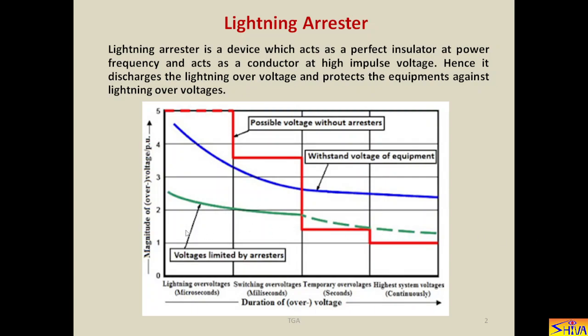Now let us see from this diagram how it protects the electrical equipments. So this is the over voltage coming in the system if it is not arrested. This is of very high magnitude. This is the withstand voltage of the equipment, that is nothing but the basic impulse level of the equipment being protected. So it indicates that in no case should the over voltage coming in the system cross this value. Therefore we have to arrest the lightning over voltage well before this magnitude or amplitude.